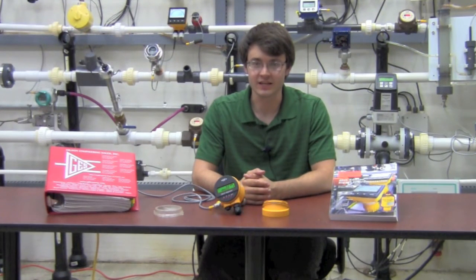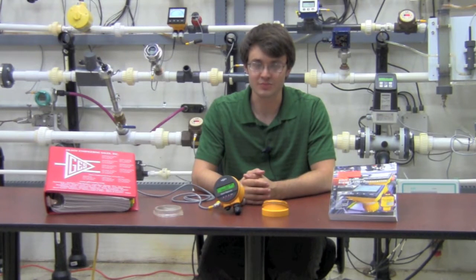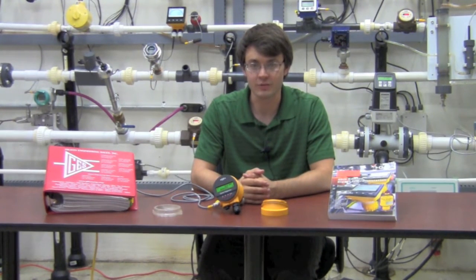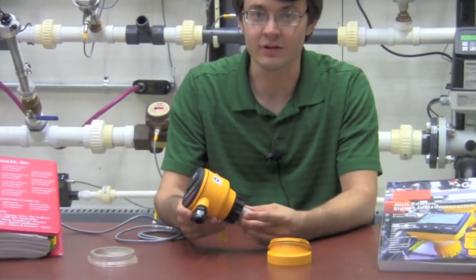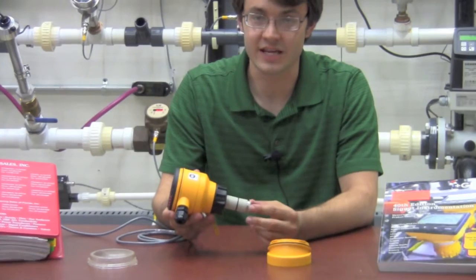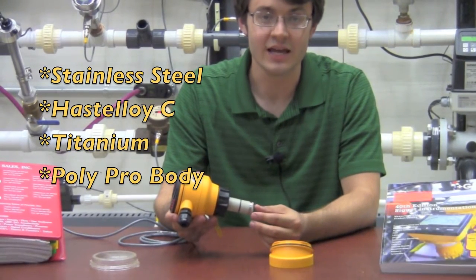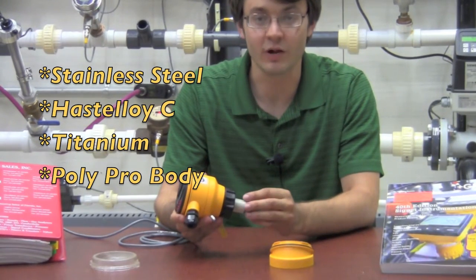The features of the Signet 2551 Insertion Magnetic Flow Meter are no moving parts, a very low pressure drop across the element, along with excellent chemical compatibility. We offer our meter with stainless steel, Hastelloy C, and titanium electrodes with a polypropylene body.